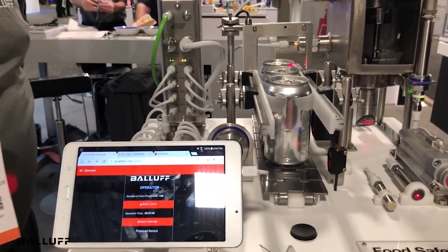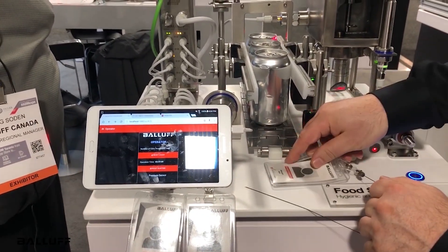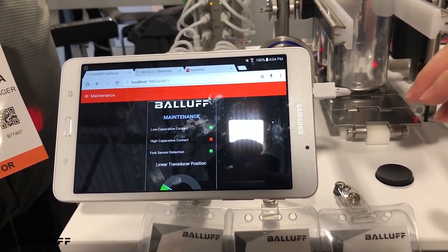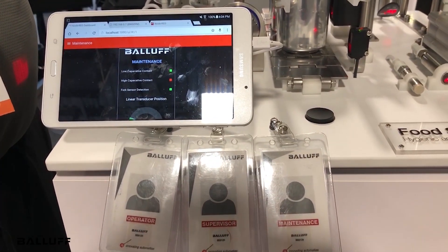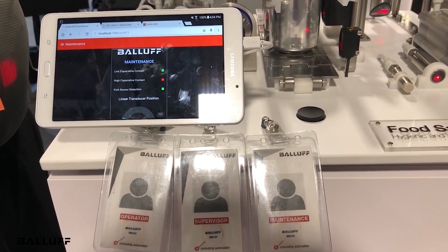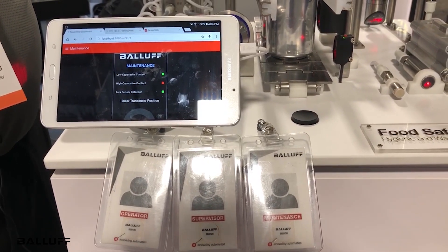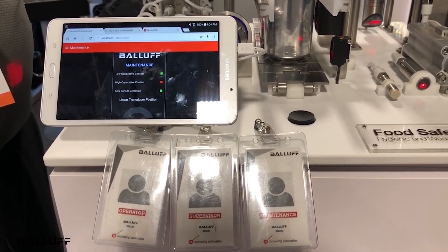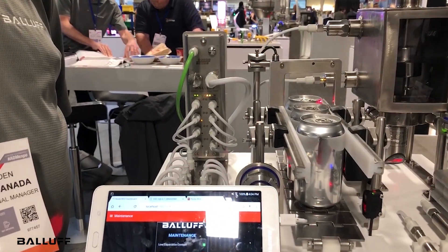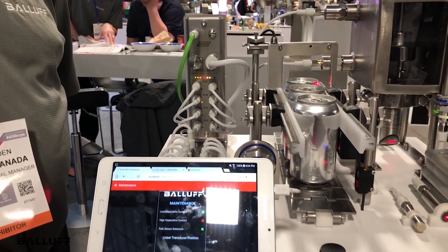If I were to take one of these badges and go over the reader here, it changes the access in the panel. The way you're describing it, our reader is actually connected back into the PLC. In this instance, because we're going through IO-Link, there's no need for a separate controller that's using up a separate IP address. We're simply tying through a normal cord set back to the IO-Link master, and then that's depositing the data directly into the bitmap of the PLC.